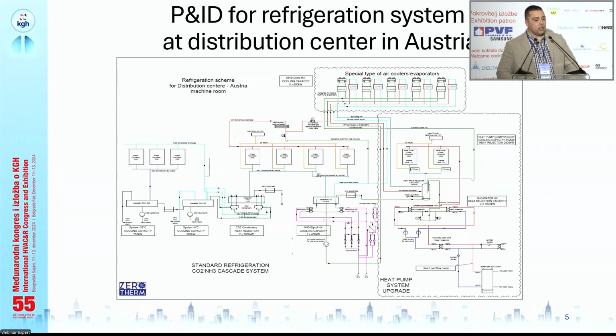On the right side, the side that is in the cloud, this is basically our heat pump system with the high temperature ammonia heat pump. We have 2 piston compressors, which have on the discharge side high temperature hot gas that goes over 133 degrees, and with the condensing temperature of 84 degrees, we go to the heat exchangers. On the other side of the heat exchangers, we have 2 circuits: the primary water circuit, which is only for safety reasons, and the second one, which is actually the major secondary water circuit that delivers 80 degrees water to the buffer tank for the heating system.